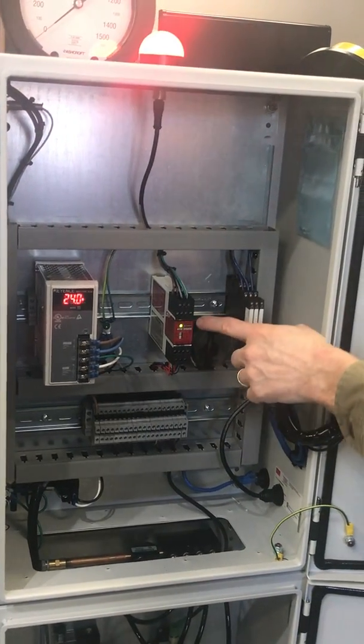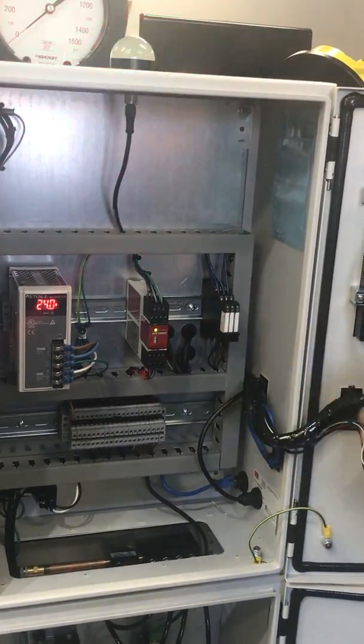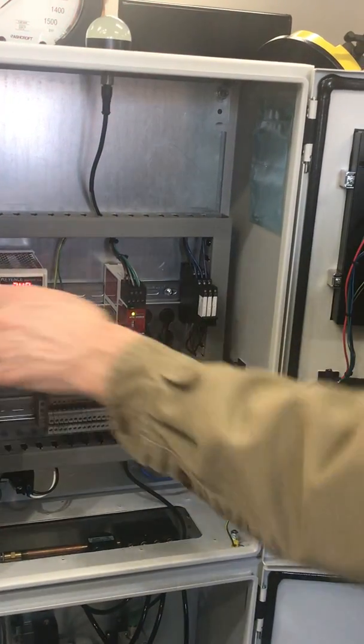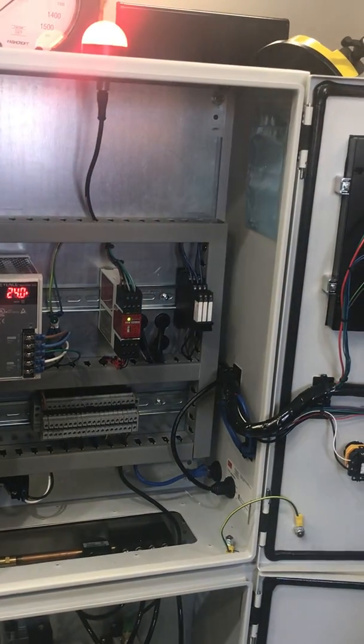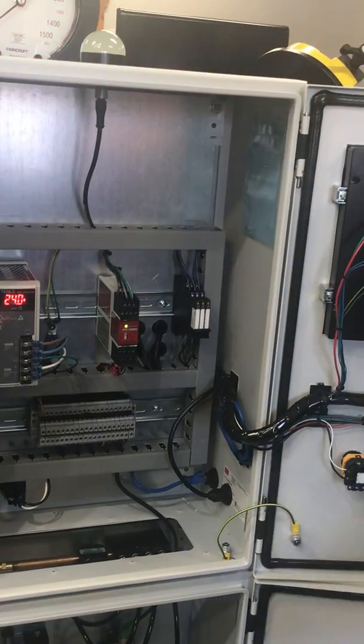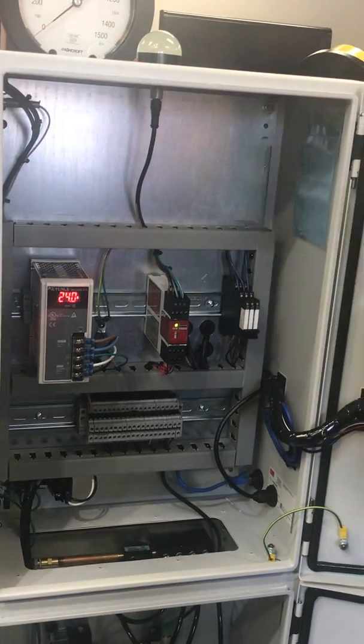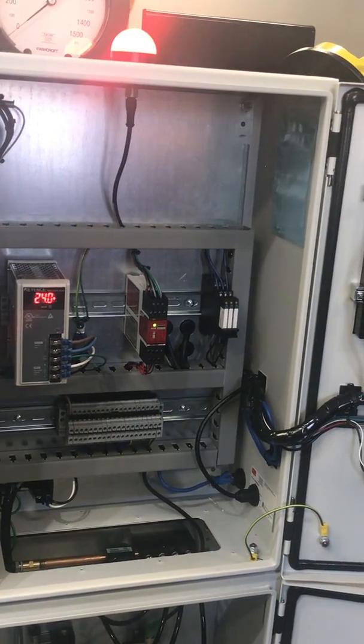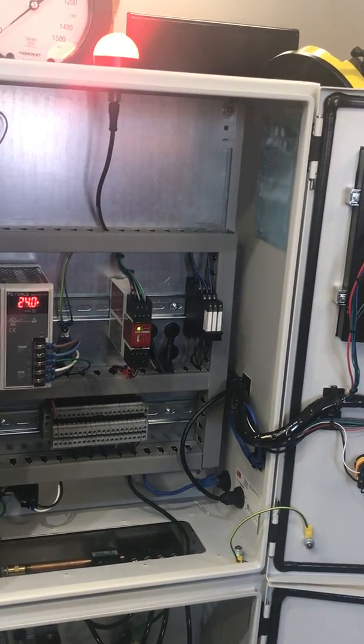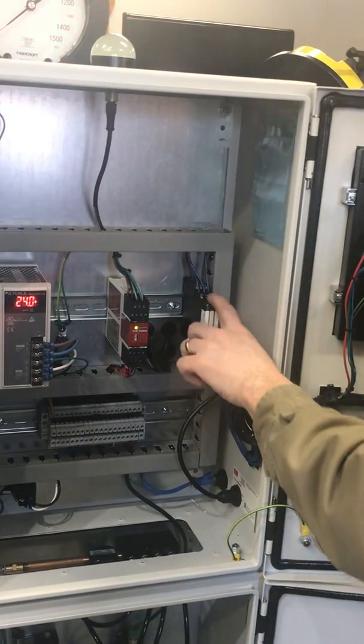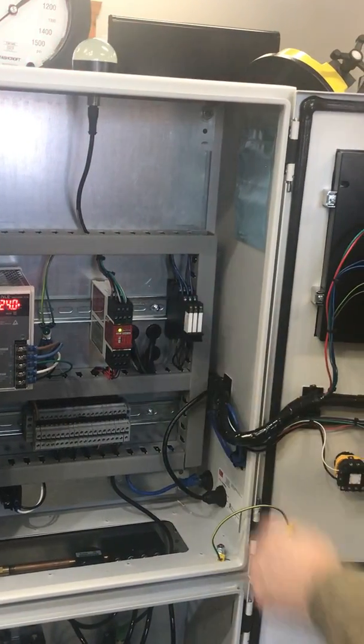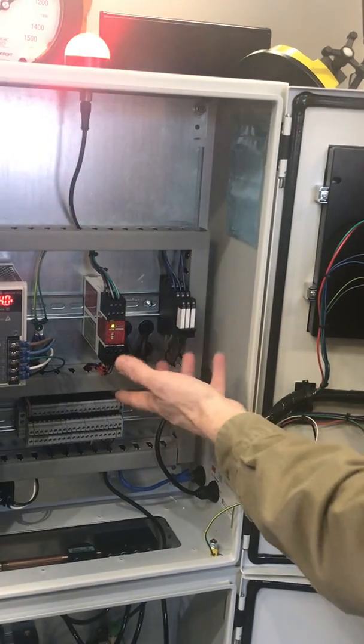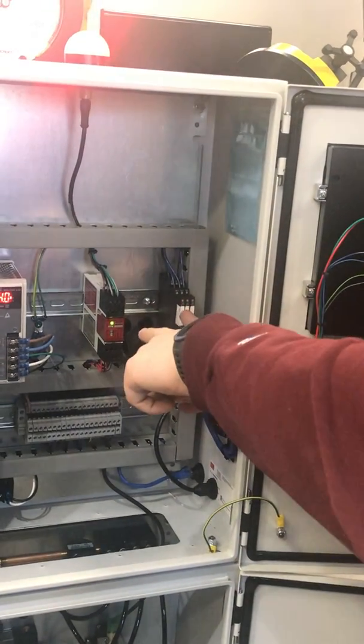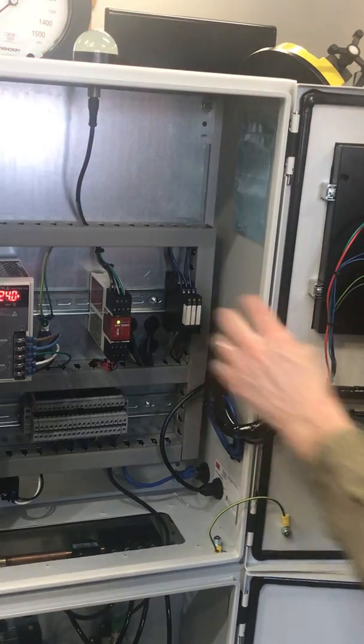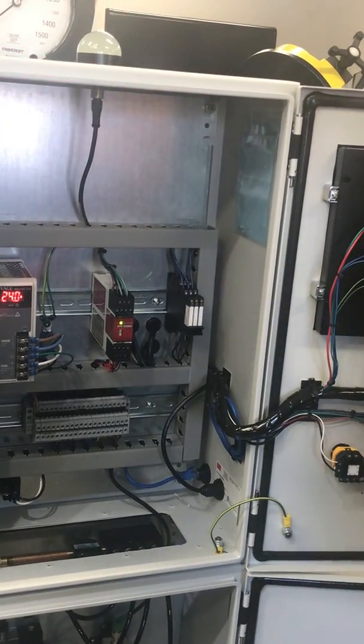And then this thing watches it like a hawk, and it'll watch whether the contacts are corroding and whatever. So this is a safety related device, and it bypasses the PLC. So if you hit an e-stop or open up the door, or there's some other kind of failure in these things, off, safe, and it doesn't matter what this guy's doing. So it's a safety circuit. And then these are some relays for some things that require a little bit higher draw, like the cabinet fan and the reset relay. You have to bridge these 2 contacts to reset that. Well, that's what one of these relays does, and I forget the other one.